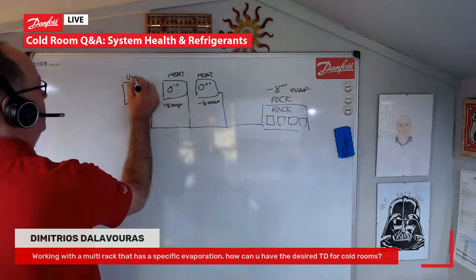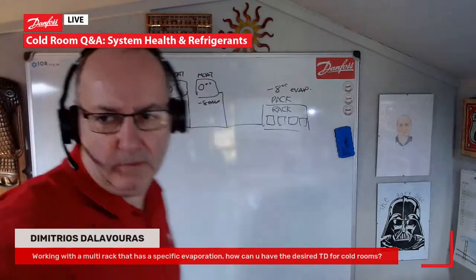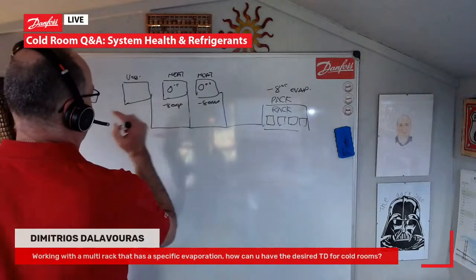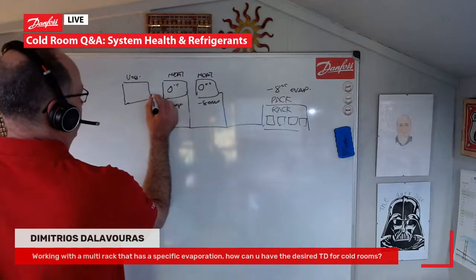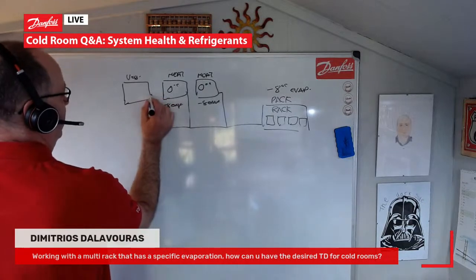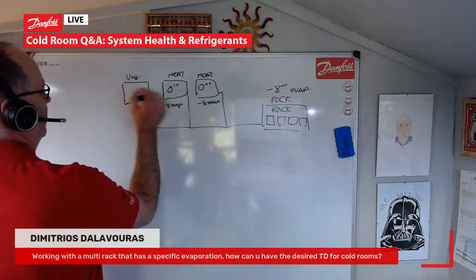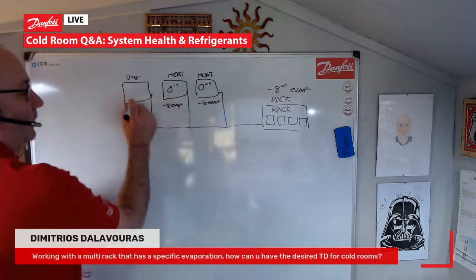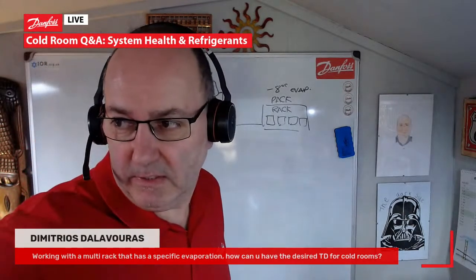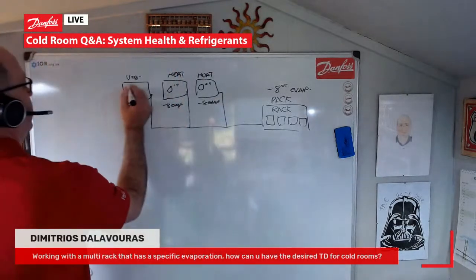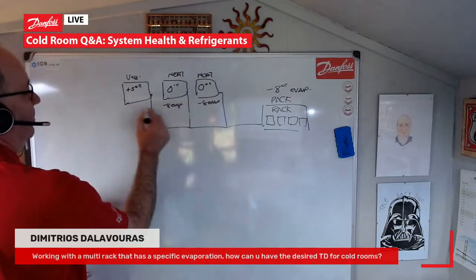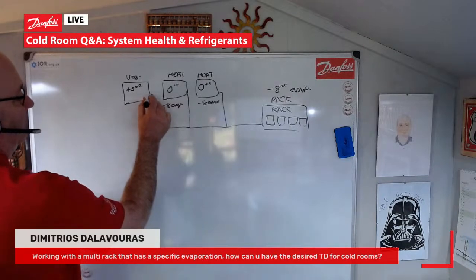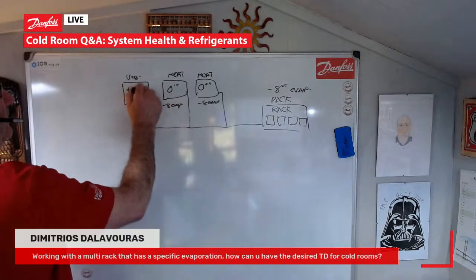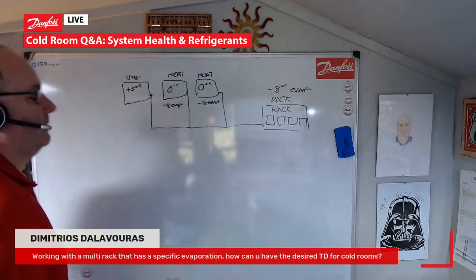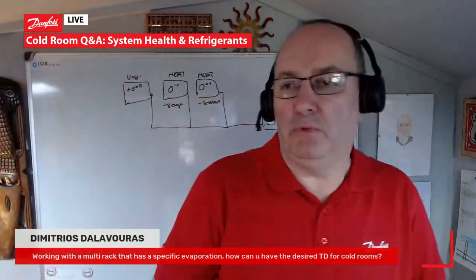And then we wanted a veg room, which was a bit warmer. So then basically you would have an evaporator pressure regulator on that evaporator just to raise the evaporating temperature in that room, so that we are, and what did we say? I think we said +5. So we would just have an EPR on that suction, basically to raise the evaporating temperature of that evaporator. Yeah, that's the simplest way to do it. So hope that answers that question.